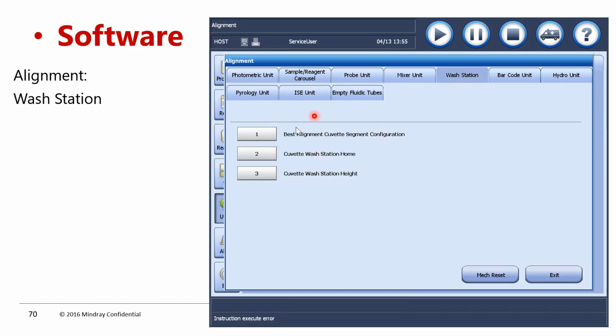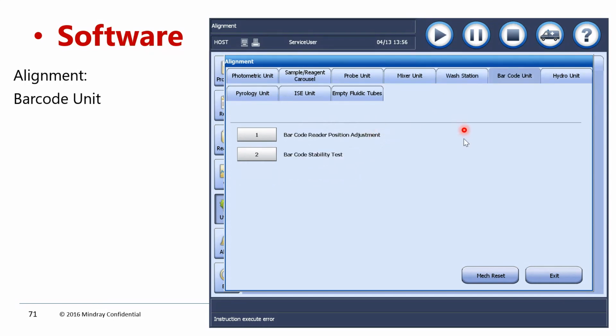So wash station alignment, you have this wash station probes you have to verify, and it is to touch the bottom but not too much. Okay, you just have to verify that there will be a tool for wash station height adjustment. You have to follow it. Home position, height, and segment configuration. And a barcode unit, as you know, this barcode is used for reagent scanning purpose, so you have to adjust accordingly.